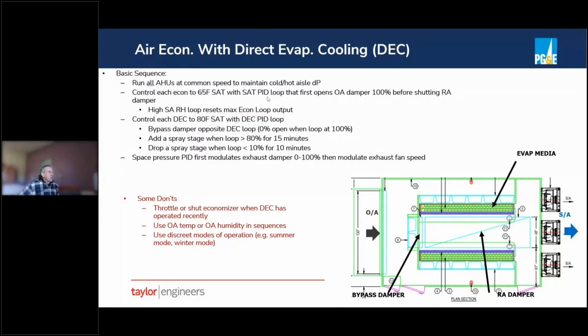And that economizer control loop will first open the outside air damper to 100% before shutting the return damper. Probably what you've seen on a lot of equipment is that the outside air and return damper operate opposite each other, so that it's 50-50, each damper 50% open. If you use this fully opening one before shutting the other, then both dampers are 100% open. And so it's just sort of a trick, if you will, for reducing fan energy, right? Reducing the pressure drop and getting the same result with less fan energy. It's a scheme we've used not just on data centers, but on everything.